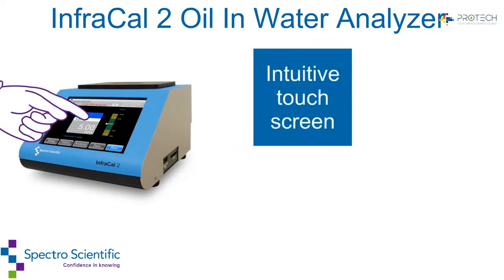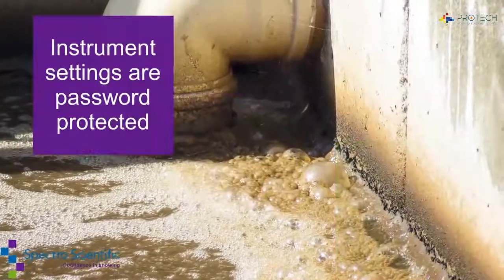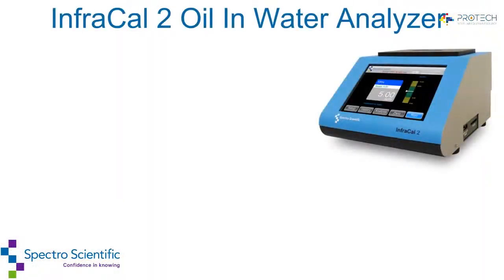The intuitive touchscreen display allows for use by non-technical personnel. Operators of the InfraCal 2 oil in water analyzer can utilize multiple calibration tables, internal data logging, and data exporting. Instrument settings are password protected to avoid unauthorized changes.